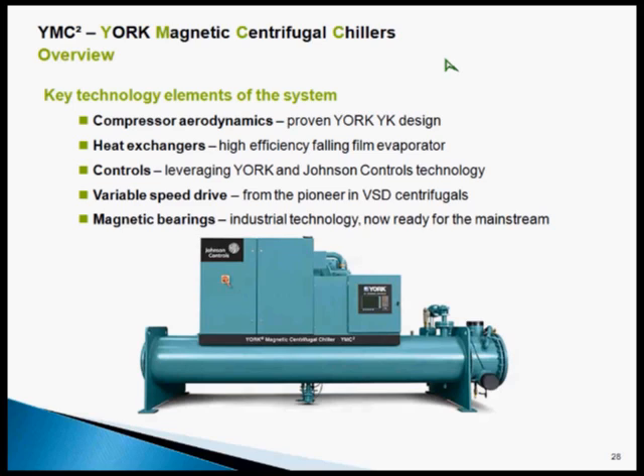I'm not going to talk about all kinds of chillers. I'm just going to talk about something interesting for you. Did you know that now there are several manufacturers, York being one of them, that make a chiller that has a magnetic bearing on the compressor? Did you know that? You're smart. So there's no oil in it. We got rid of that one fluid that was a pain, that we have to keep maintaining the oil pressure and oil temperature and all that kind of stuff. We got rid of that whole thing. So now it's magnetic bearing, oil-free.